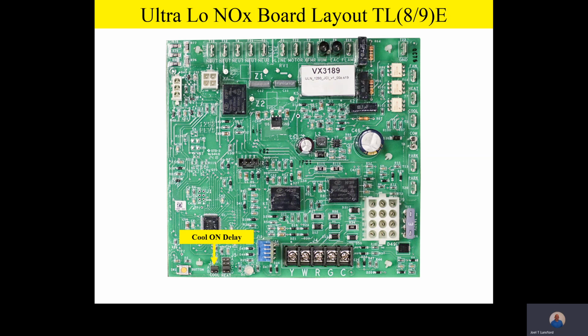And please write this down. The A position is 6 seconds and the B position is 24 seconds. So again, if you have a humid environment, you can move that cool on delay down to the B position, and that will delay the indoor coil, or excuse me, the indoor fan from coming on for 24 seconds in the B selection.